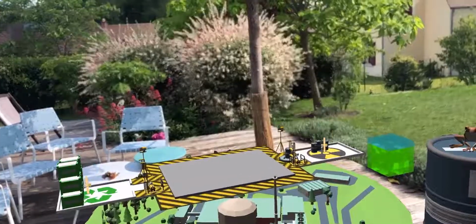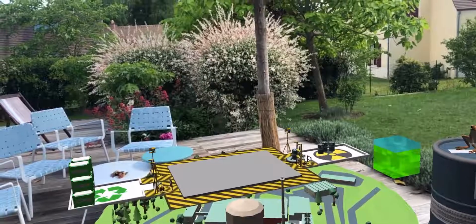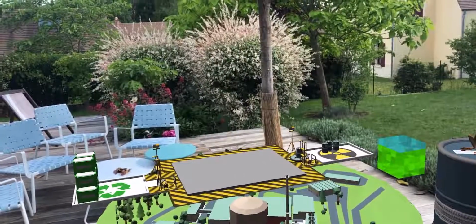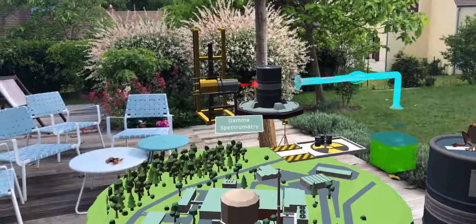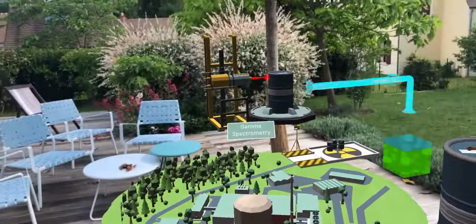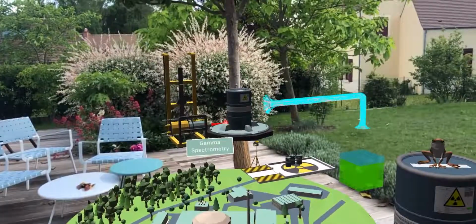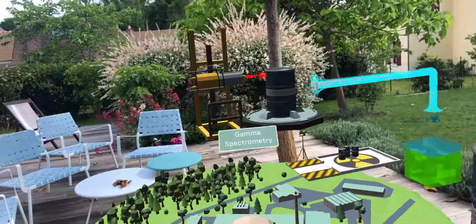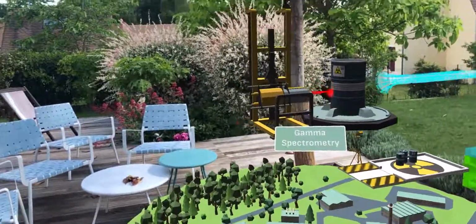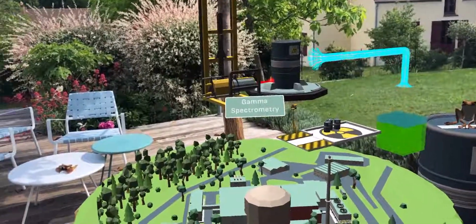Each drum and container, once filled and sealed, is catalogued and labeled, while the content is described, photographed and measured. And here is the machine used to measure the radiation coming from inside the drums. It is called a gamma spectrometer and measures precisely all gamma radiation. Since we maintained the homogeneous groups, we can calculate alpha and beta radiation by measuring only the gamma radiation. Do you still remember that we established the ratios earlier?